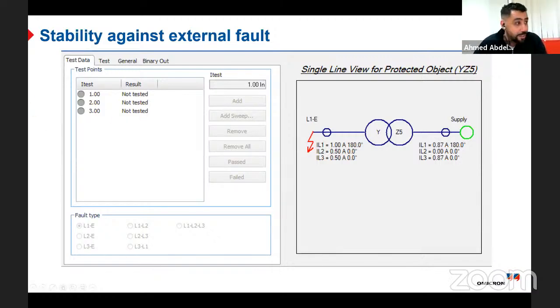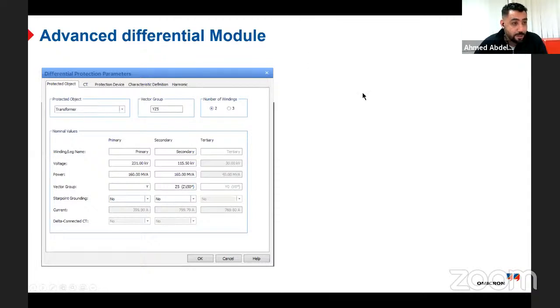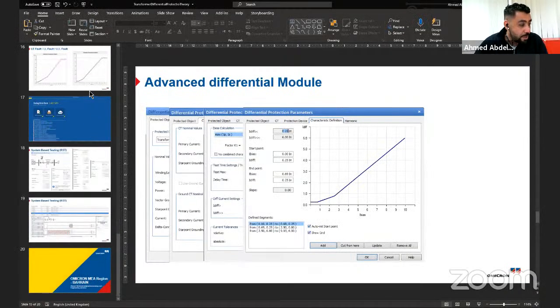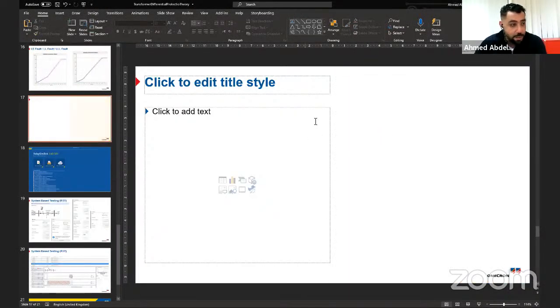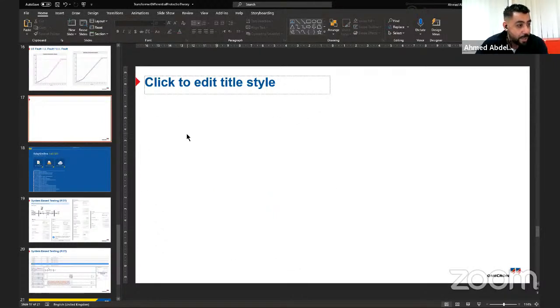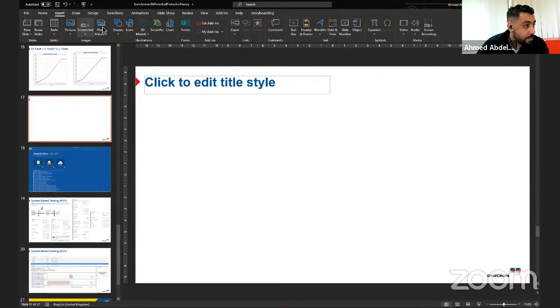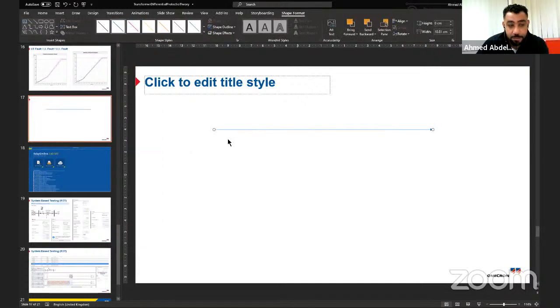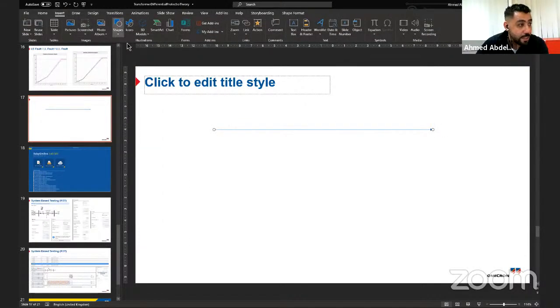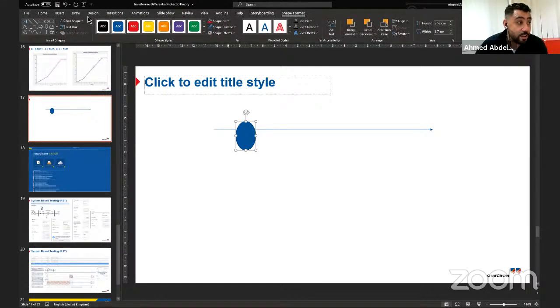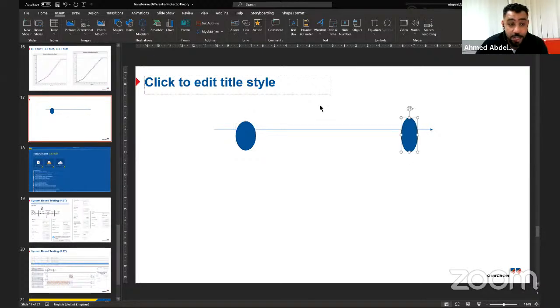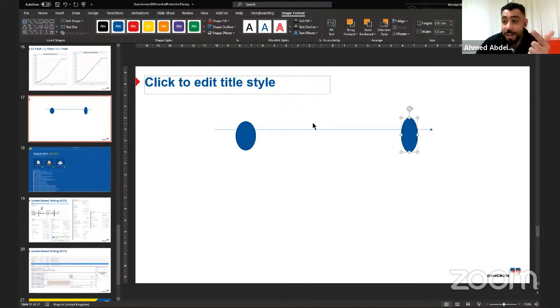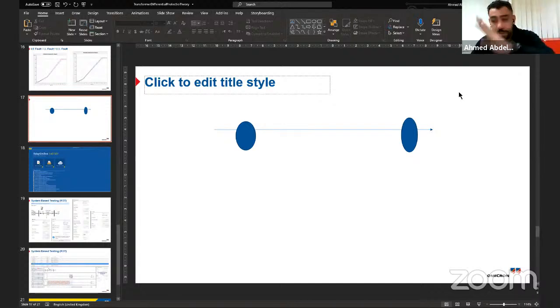I can draw it for you here. Just a minute. Okay, so it is very easy. For example, this is the conductor. I will have here a CT. This is the CT from the neutral side of the generator, and the other CT will be here at the high voltage side. In between, you will take the generator and the transformer, nothing else. Then the CT from the neutral side of the generator will be the low voltage side of the transformer, and this will be the high voltage side of the transformer. And the generator doesn't have any effect on the characteristic itself. It might add more errors, but in the slope, no.